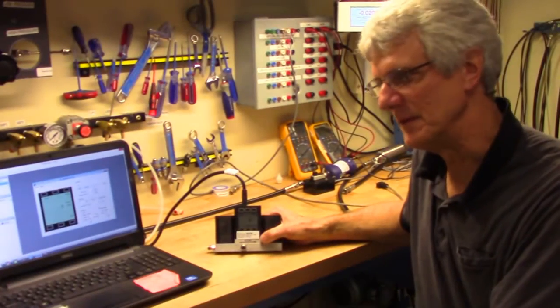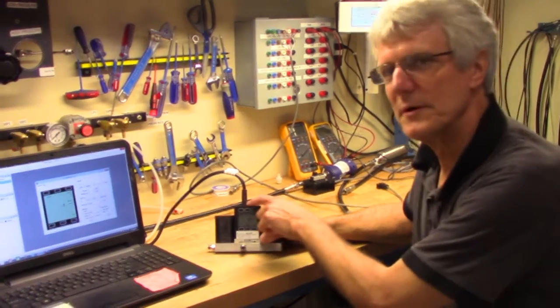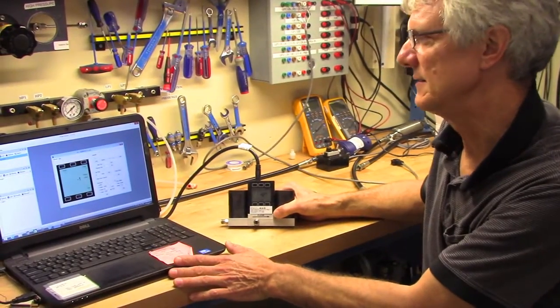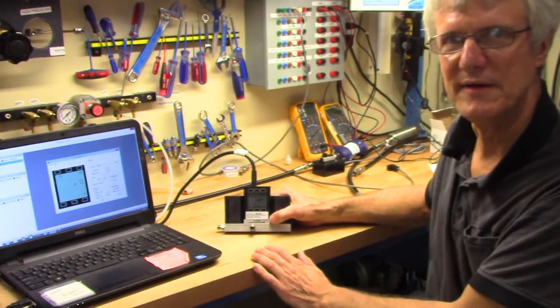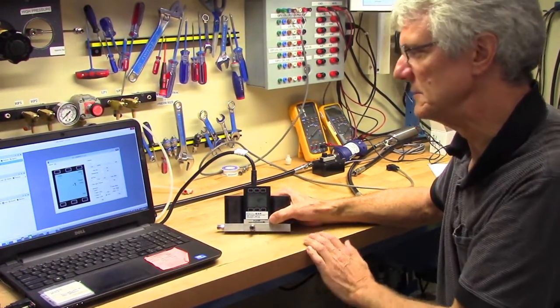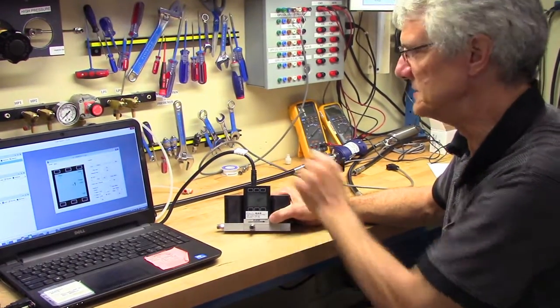The second method for controlling the PID loop on the EPR 3000 is through the serial port and using appropriate software on a PC. In this case, we're using the FlowVision software, which has an option for changing all the values. But in order to communicate with the computer, you need to change the control setup from the front panel to the RS-232 port.